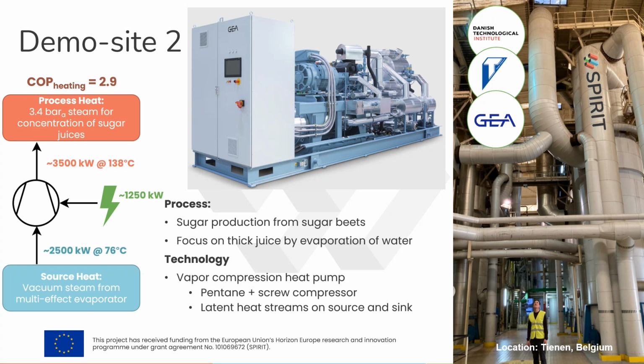At the end of this process, we have a vacuum steam available from the multi-effect evaporator, and we plan to upgrade this in temperature from around 76 degrees up to 138 degrees to produce the 3.4 bar steam that can be reused in the process.